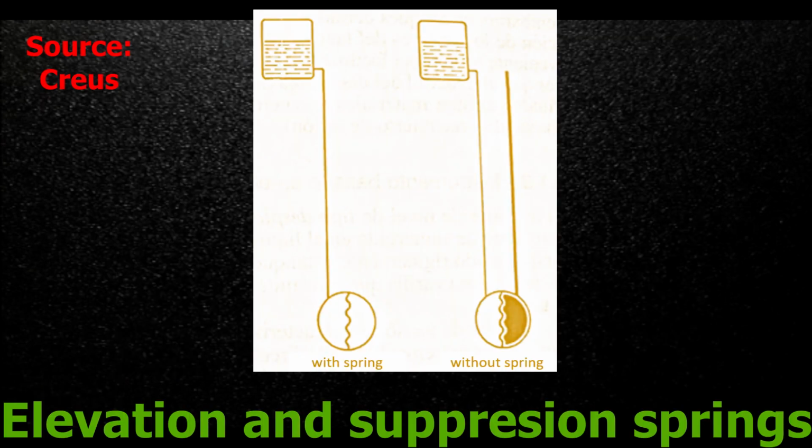If the tank is elevated and the meter is in a much lower part, the column of liquid that goes from the minimal level to the meter is greater than the variation of the level itself, so its measurement is made on a very small part of the scale. To correct this, elevation springs are used, which are applied to the transmitter's force balance bar and produce a force that adjusts equal to the column of the liquid that I mentioned. As with zero suppression, digital instruments have an algorithm for zero elevation.